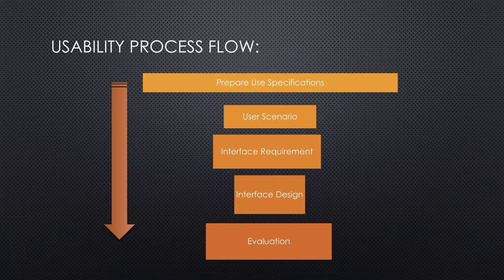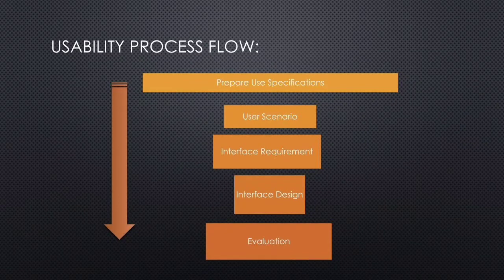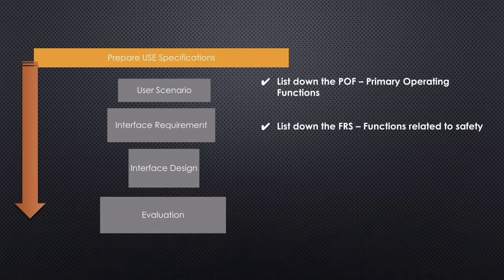Next, we have to consider the usability process flow while designing or developing a product. The steps are: prepare user specifications, user scenarios, interface requirements, interface designs, and evaluate those things. First, in preparing the user specifications, we have to list down the primary operating functions and function-related safety for the user.